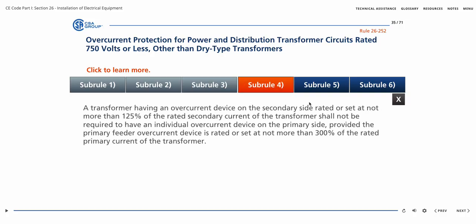Subrule 4 requires that a transformer having an overcurrent device on the secondary side rated or set at not more than 125% of the rated secondary current of the transformer shall not be required to have an individual overcurrent device on the primary side, provided the primary feeder overcurrent device is rated or set at not more than 300% of the rated primary current of the transformer.